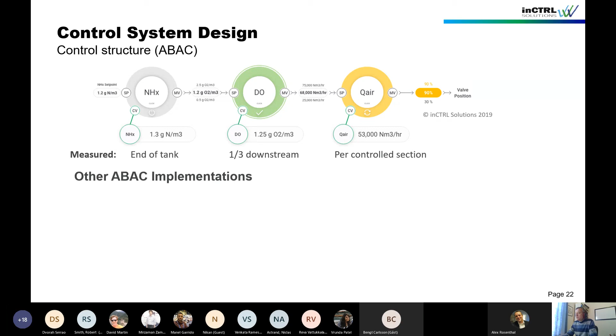So one is called direct ammonia-based aeration control, where the ammonium controller is going directly on the valve position or the airflow loop. I clearly do not recommend that. One thing is it's very difficult to tune, and it's also not protected against high ammonia load. Yeah, so clearly not something I would recommend. Feed-forward feedback combination, you see that popping up everywhere. I would say typically not required. It increases cost mainly for sensor maintenance and quality control because you have much more sensors.